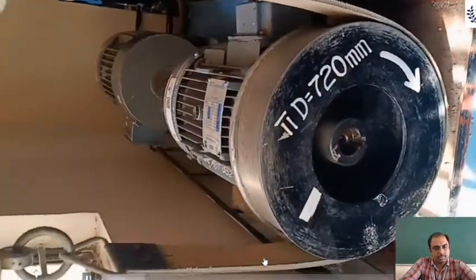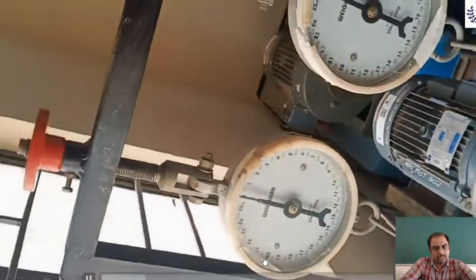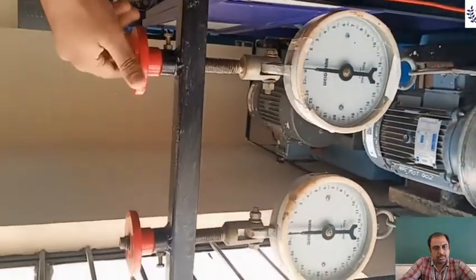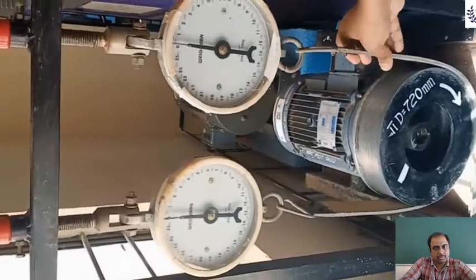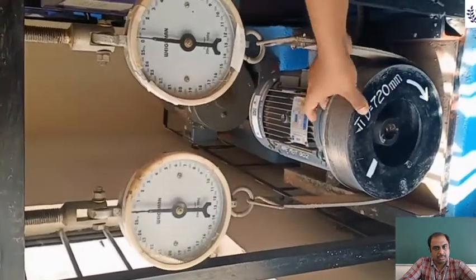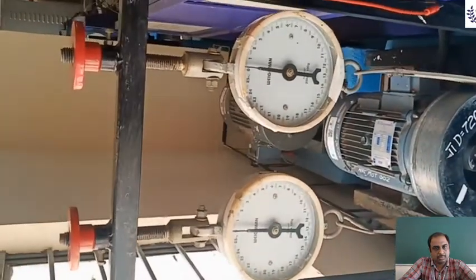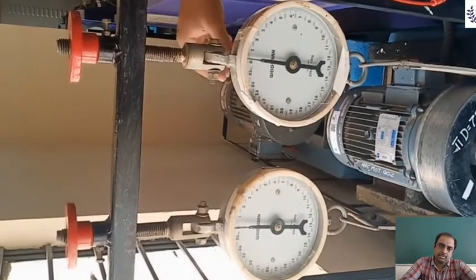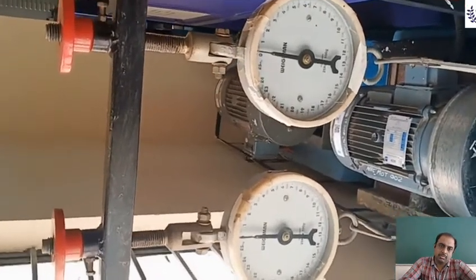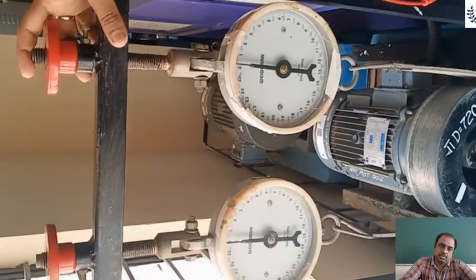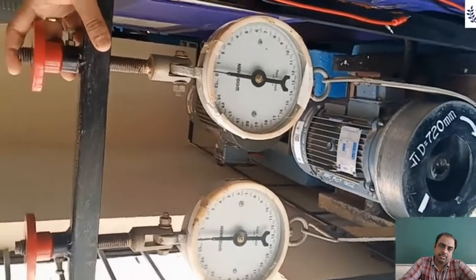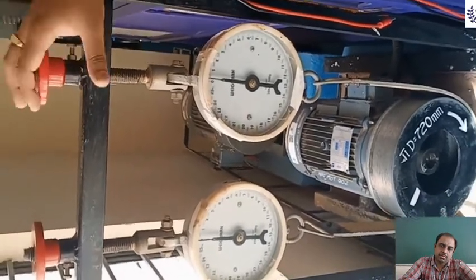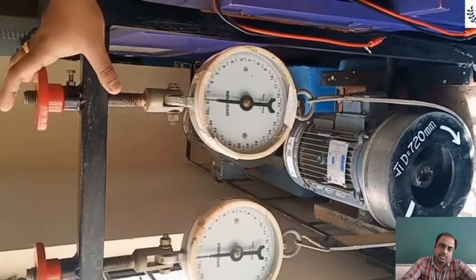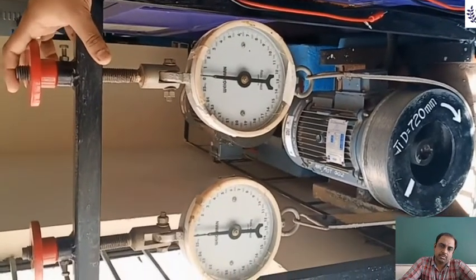And this is S1 and S2. This is the spring balance load. This is the brake drum pulley. By applying the pulley, the belt will be tied to this motor. Then we came to know that the motor is on load. The rated current is 4.8 ampere at 415 volt. The speed is 1440 rpm. This is a squirrel cage induction motor.